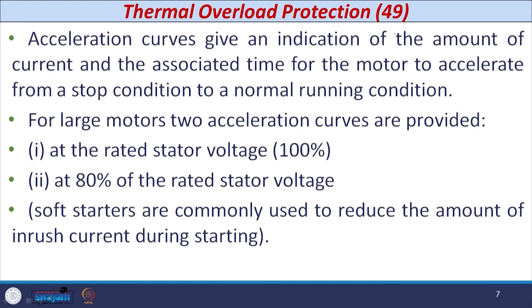This time period is always associated with some voltage — whether you start the motor at rated voltage or some reduced voltage. For large motors, two acceleration curves are specified by the manufacturer: the first at 100 percent rated voltage, and the second at 80 percent of the rated stator voltage. Soft starters are commonly used in induction motors to reduce the starting current, which is 5 to 6 times the full load current, but keep in mind this is not a fault and the protection device must discriminate between these two phenomena.